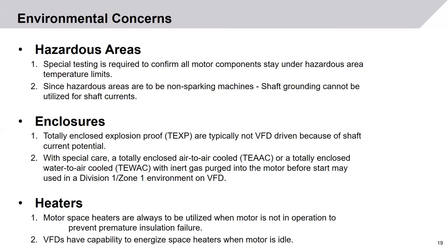Another concern is space heaters. Motor space heaters must always be utilized when the motor is not in operation to prevent premature insulation failure. VFDs have the capability to energize space heaters when the motor is idle, without requiring someone to manually turn them on.